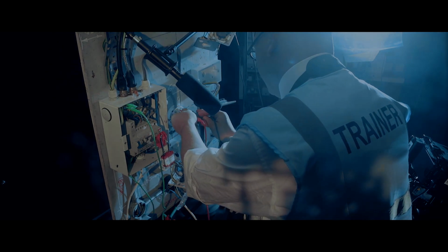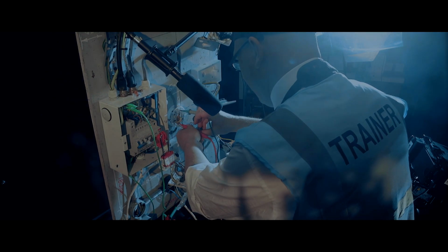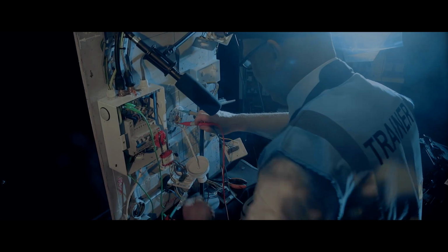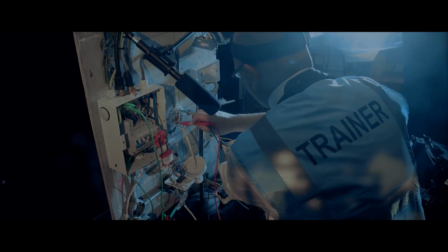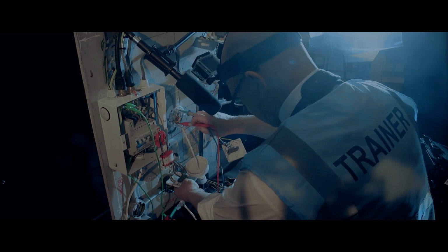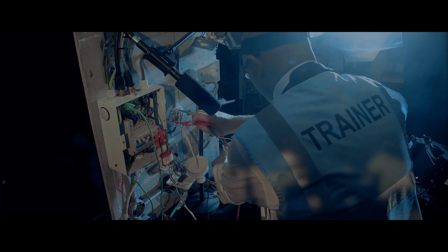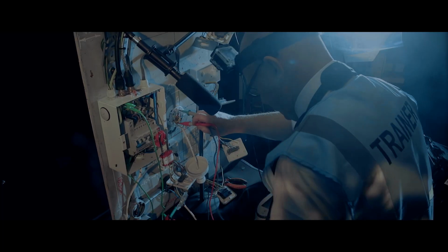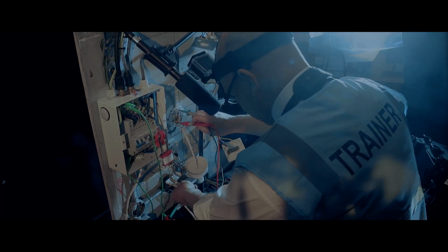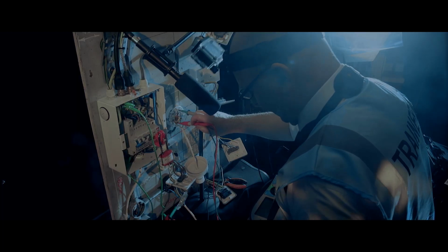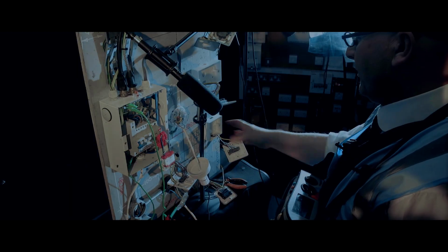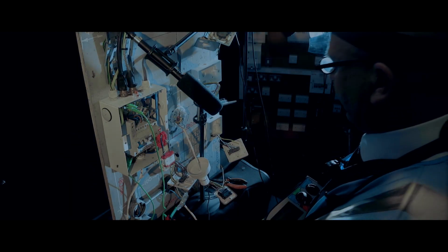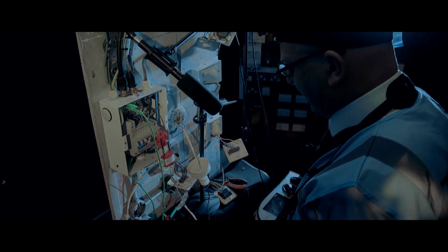Okay, I can then switch that one off if I want and go on to do the R1, R2 from the switch line of my ceiling rose to the CPC of the light circuits, and go between the two switches to find the highest reading. Now, the highest reading in this instance looks to be 0.11. The other reading is 0.09. So I take 0.11 as my R1, R2, the higher of the two readings.